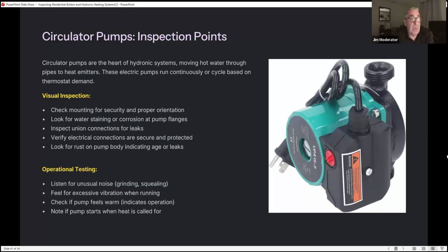Circulator pumps, inspection points. Circulator pumps are the heart of the hydronic system, moving hot water through pipes to heat emitters. These electric pumps run continuously or cycle based on thermostatic demand. Visual inspection: you want to, again, check that the mounting is secure and the orientation is proper, look for water staining or corrosion at the pump flanges, inspect the union connections for leaks, and verify electrical connections. We've been through this. And look for rust on the body indicating leaks.